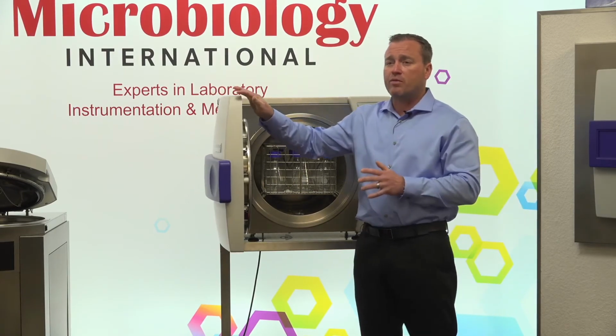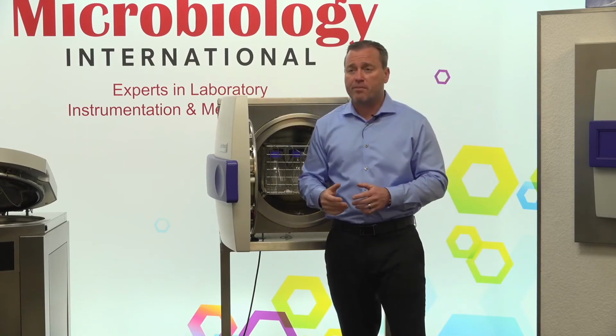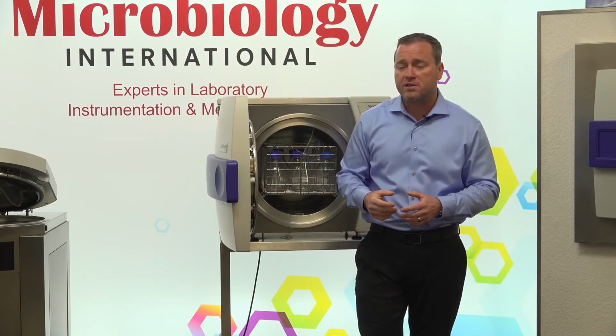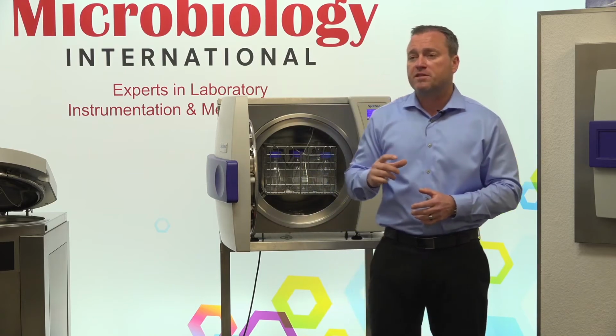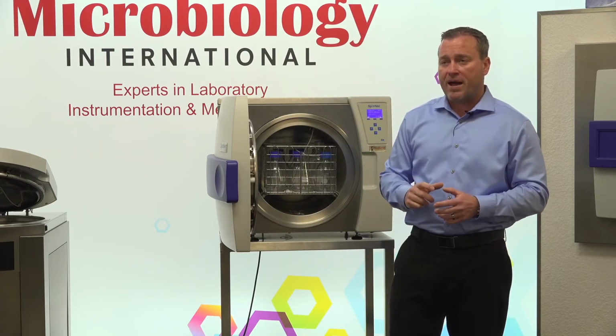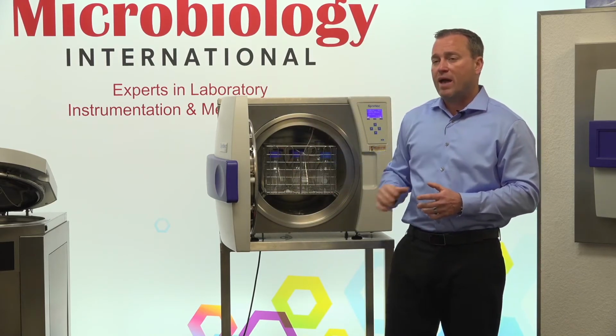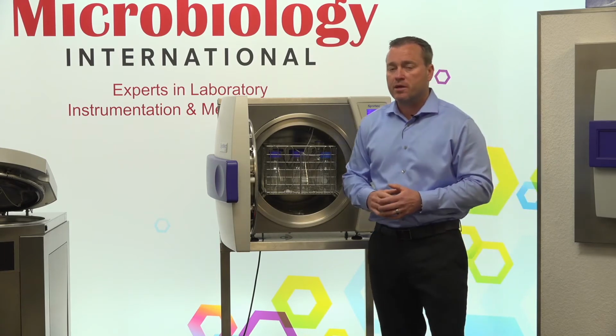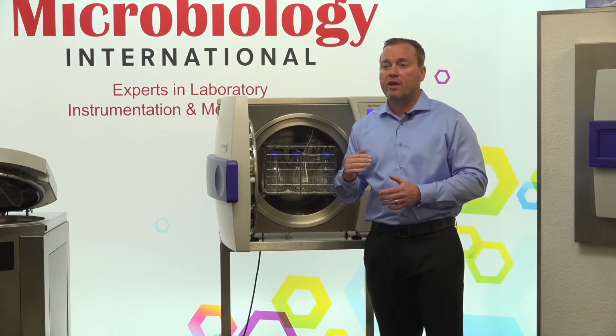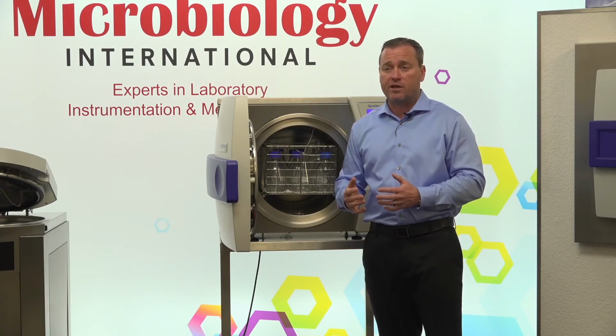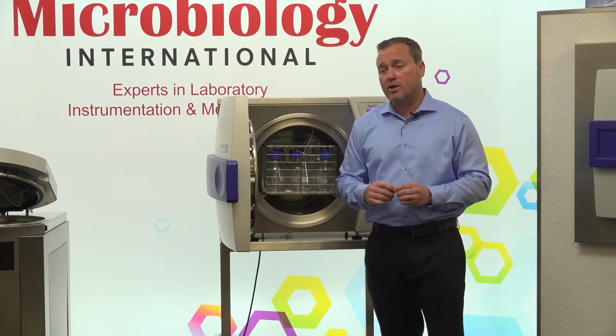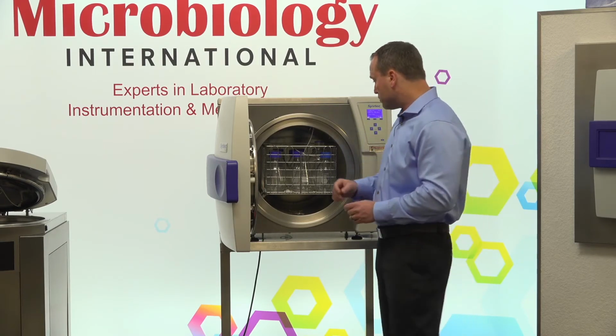With the keypad on this instrument, we don't offer the capability to do 21 CFR compliance. A lot of the specific programming for username and passwords isn't on here. We have standard passwords for this instrument, so you would just have to determine which level of password you want to get each individual operator, but there are not unique passwords for these systems.